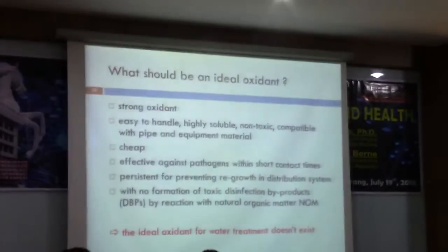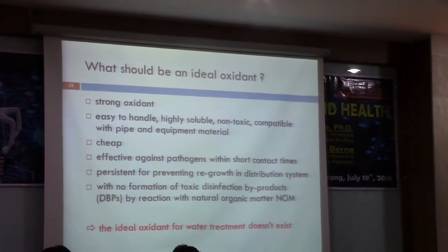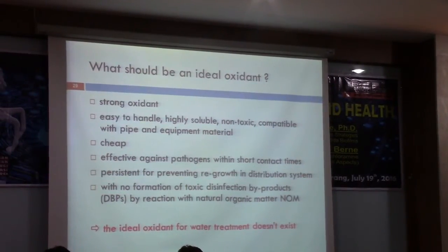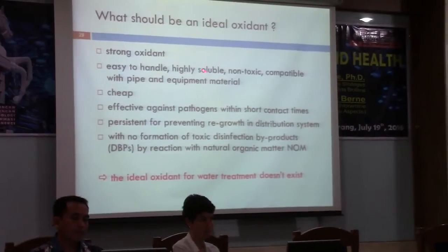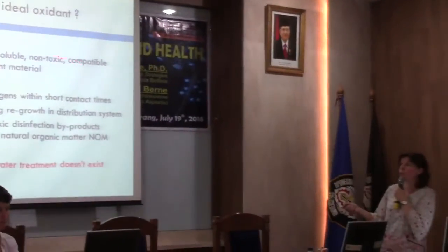So what should be an ideal oxidant? It must be strong to do a complete oxidation, or as far as possible complete oxidation, of natural organic matter, micropollutants, and so on. It must be easy to handle, safe to handle too, highly soluble, non-toxic, and compatible with the materials in contact with the water, for example to avoid corrosion. Cheap, and very effective to do disinfection, with very broad biocide properties.